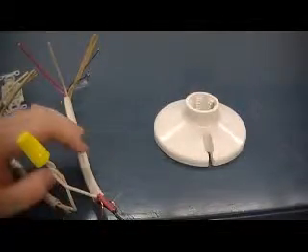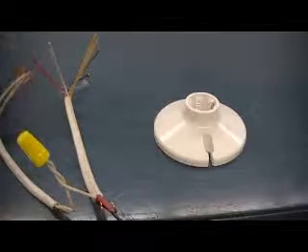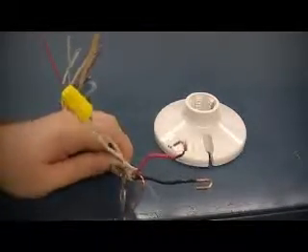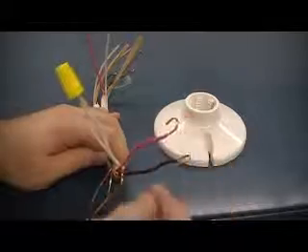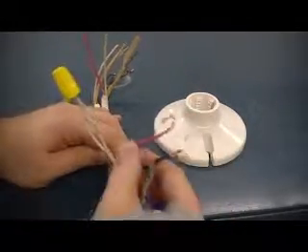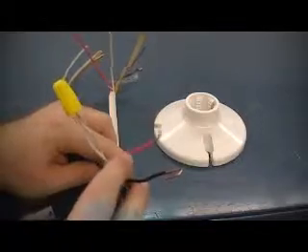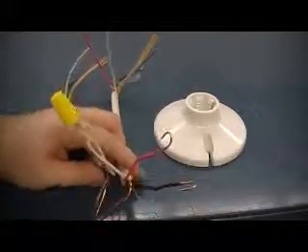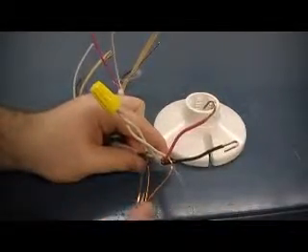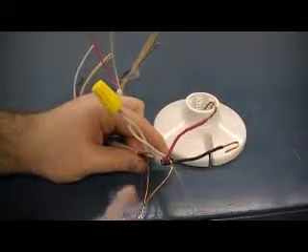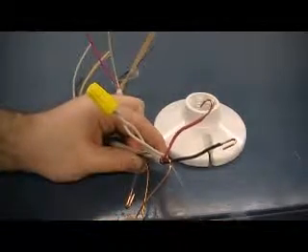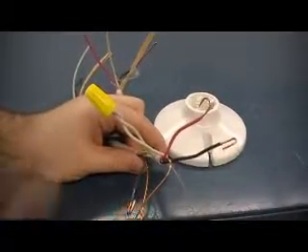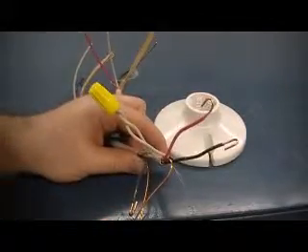On the second one, pretty much the same process. Okay, your grounds twist together, wire nut your neutrals. Okay, the black and red coming in from your 14-3 from the first switch will connect to the top screws on the second three-way switch. The hot wire going out to your light on the 14-2 wire will go to your common. Okay, so on the first switch that was power coming in on common. On the second one it's power going out on common.